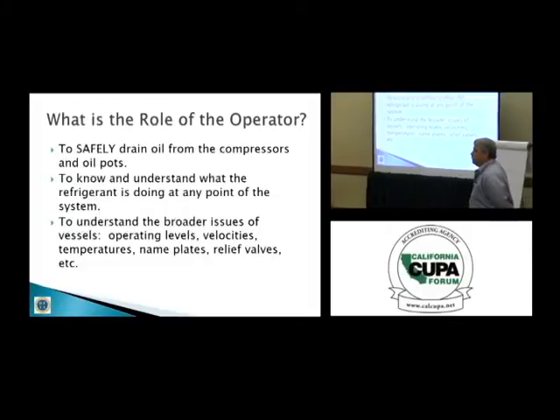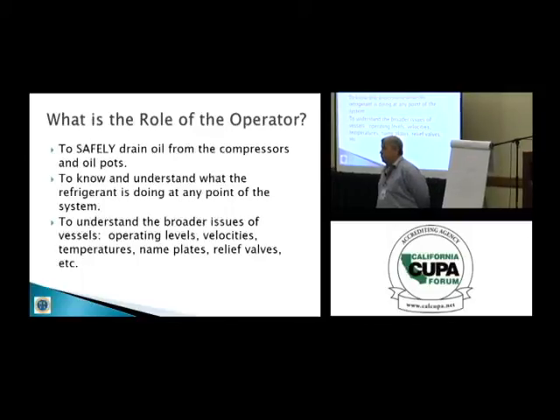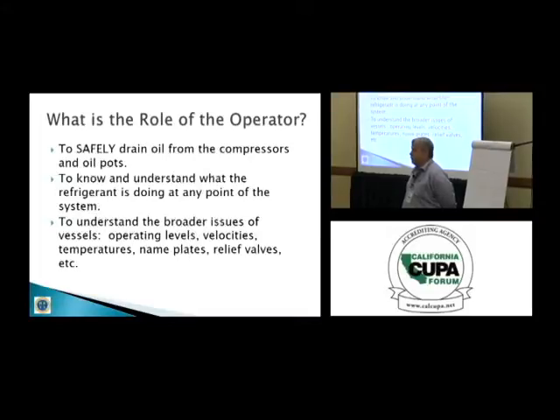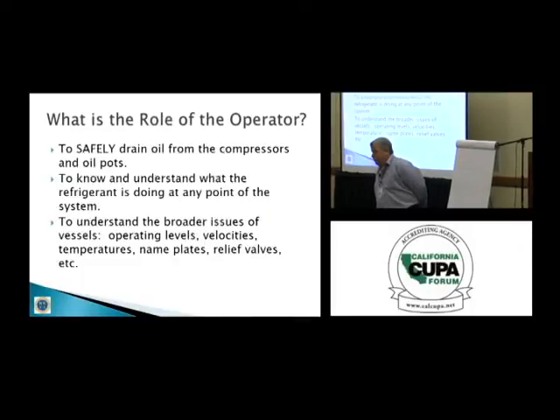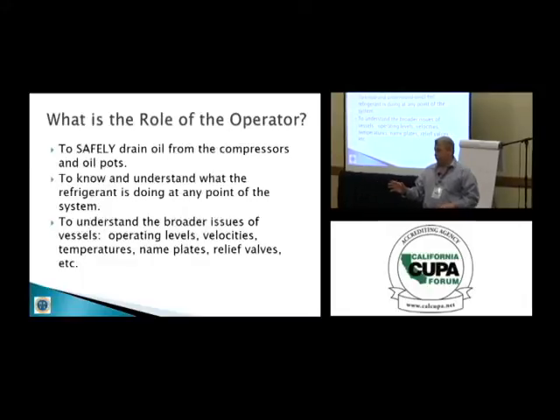How does that work? The way it's worked out for me is, because the manufacturer is no longer in business, the National Board gives that certified shop the information, and they create a data plate with the information, and then it's affixed onto the vessel. One of the things that we're doing now is when we buy a vessel that's going to be insulated, it comes with two data plates. It has the one that's on the shell and gets covered up, but it's also got one on the structural leg.